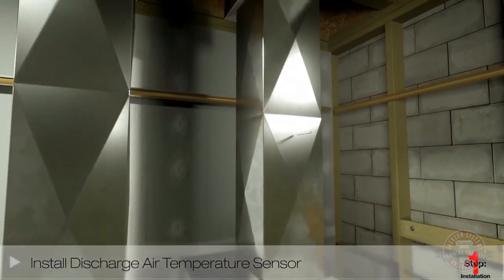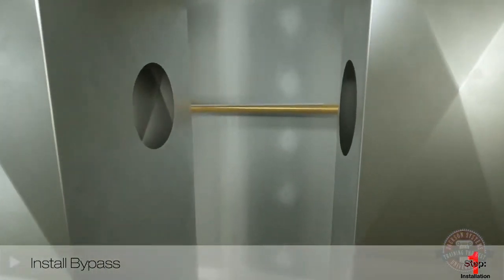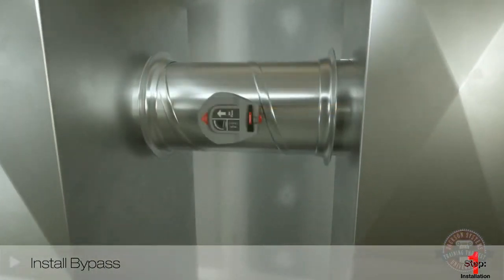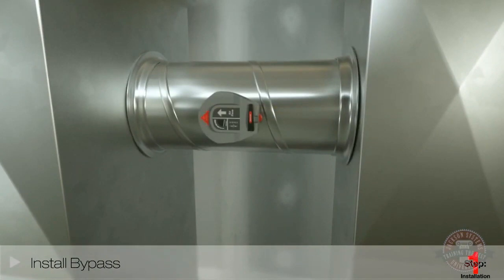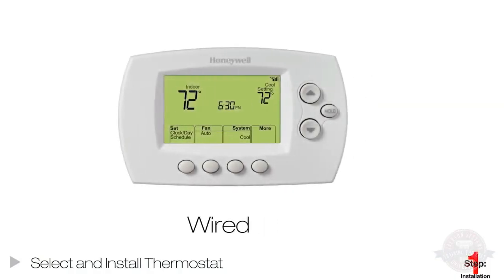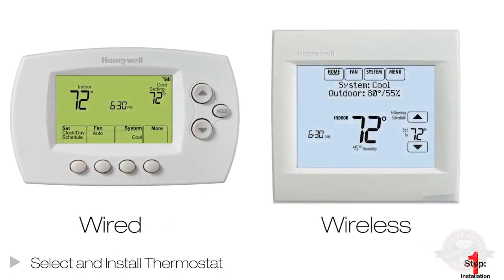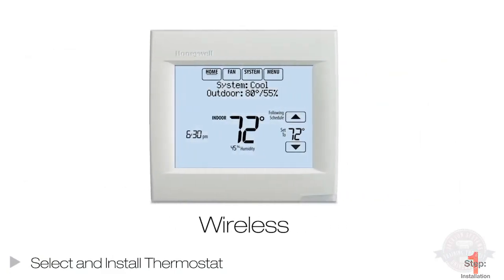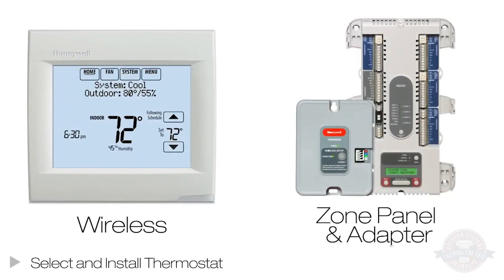Install and wire the discharge air temperature sensor in your supply duct. Next, install the bypass damper between the supply and return ductwork, making sure the arrow is pointing in the direction of the airflow. Then, install your thermostats. You can use standard wired thermostats, or you can use Honeywell RedLink thermostats by combining an 8Z432 or 8Z332 TrueZone panel with a wireless zoning adapter.